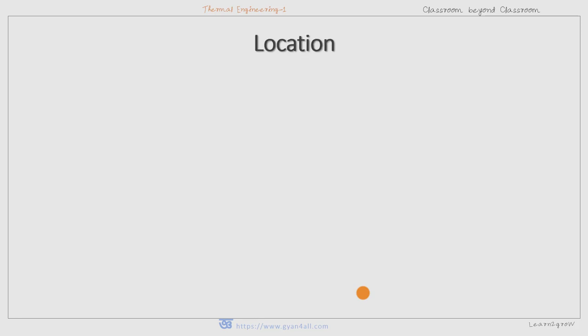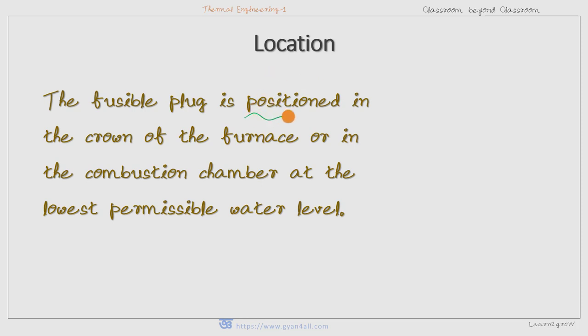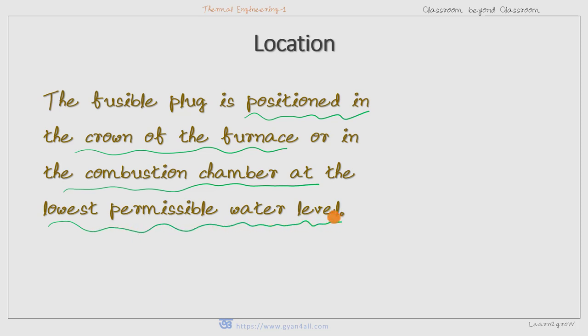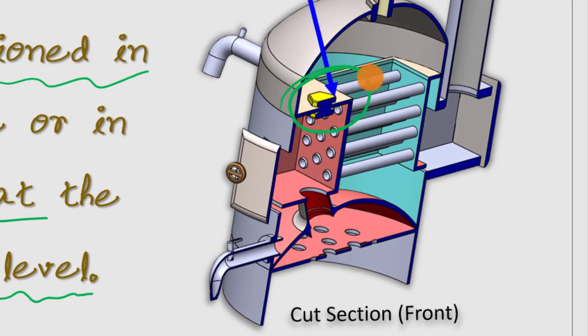Now, what should be the location of the fusible plug within the boiler? The fusible plug is positioned in the crown of the furnace, above the furnace, or in the combustion chamber at the lowest permissible water level. Let us see with the help of a Cochran boiler cross-section. In this boiler, this is the lowest possible level of water because it is continuously exposed to the hot combustion gases from the furnace, and that is why this is the position of the fusible plug — above the furnace, below which the water level should not go down.